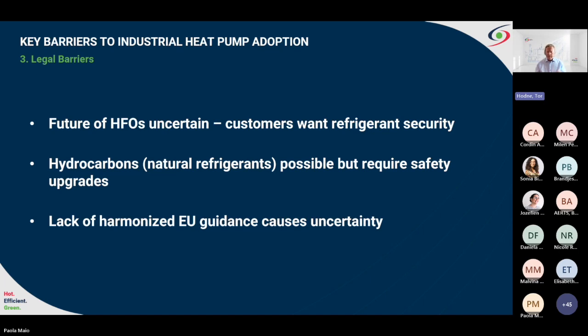Fortunately, as mentioned by Gordon earlier, our heat pumps can also run on natural refrigerants like hydrocarbons, but these are flammable and toxic, and we then run into safety codes which need to be tackled. So for us, there's a bit of a catch-22, HFOs versus HCs. Each has pros and cons, and we hope that legal uncertainty can be overcome in the near future so that we can also have a clear long-term framework to work within.